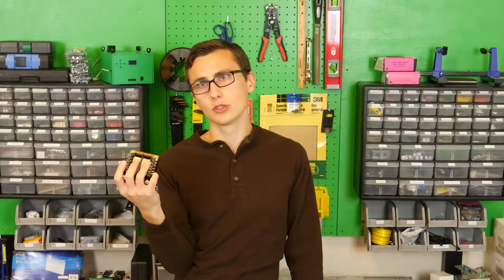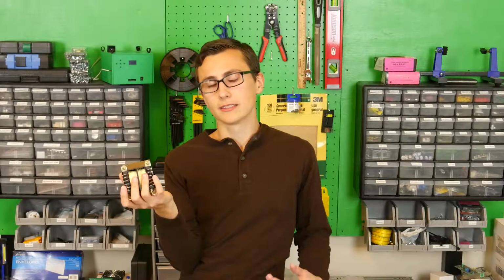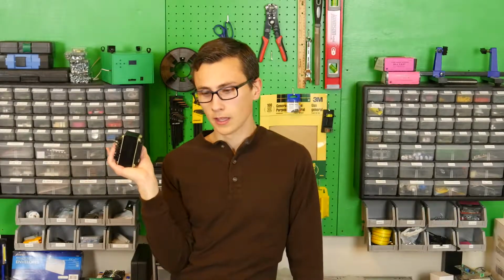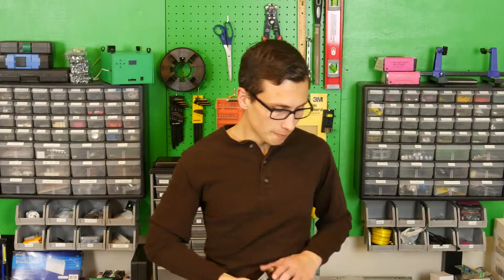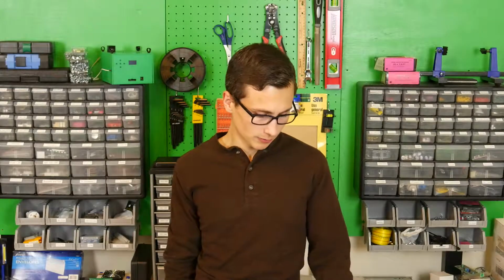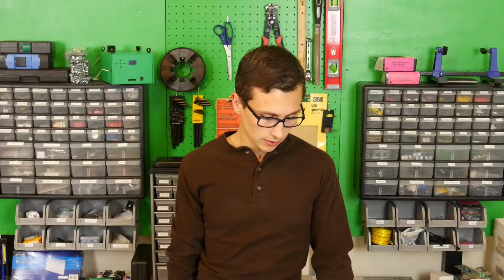What that means is I need to short neutral to ground as if it were tied back in the distribution panel. That's not normally something you'd do, but some equipment might demand those two are the same potential, otherwise they'd have leakage currents in places they weren't designed for, and that could really screw things up. I just don't want to take that risk. So by shorting the two together, it'll look like a voltage source from ground to line, and approximately 0 volts between neutral and ground - exactly as if you'd plugged it into the wall. That's why we're doing it.